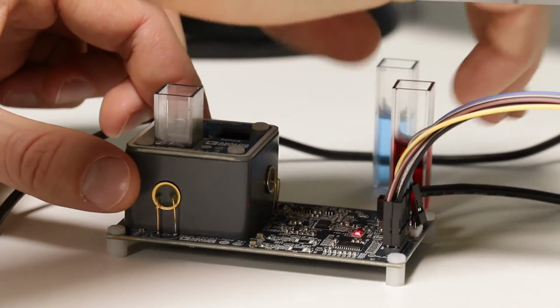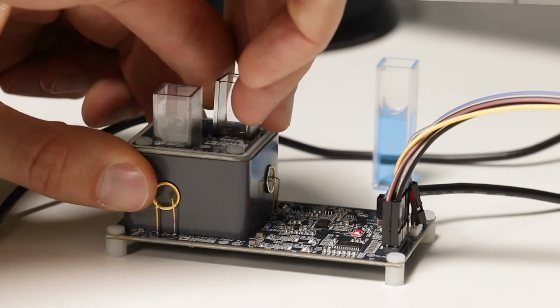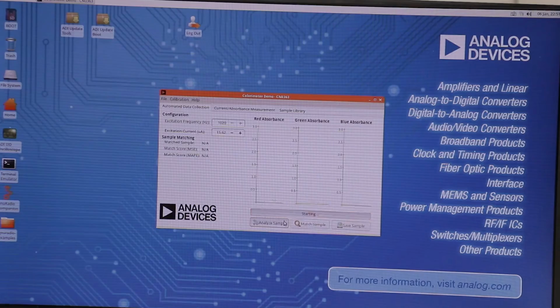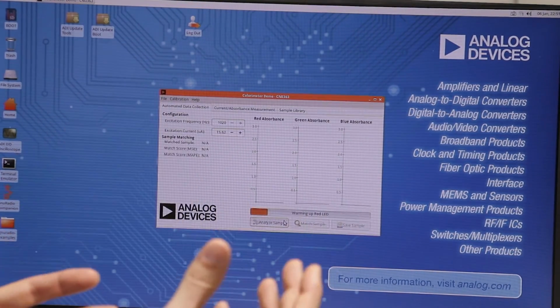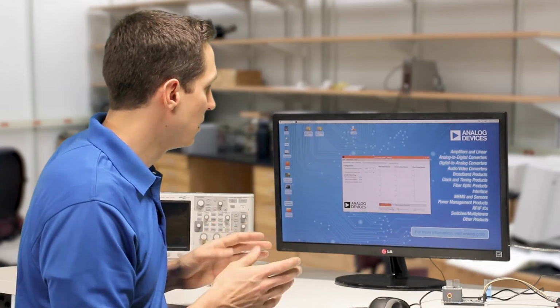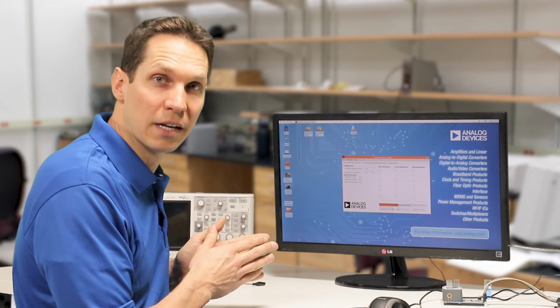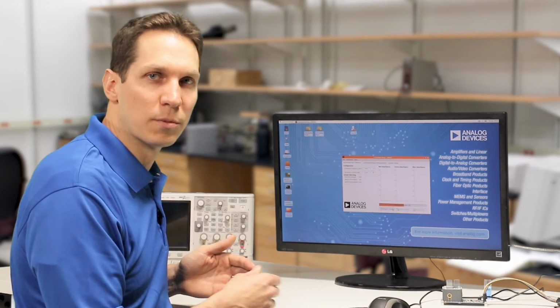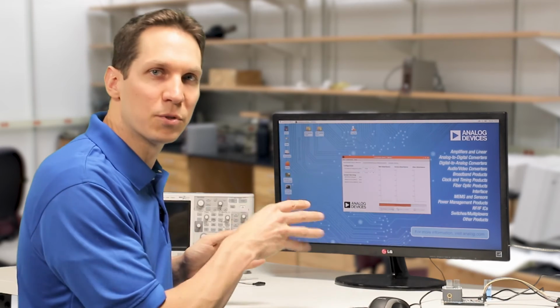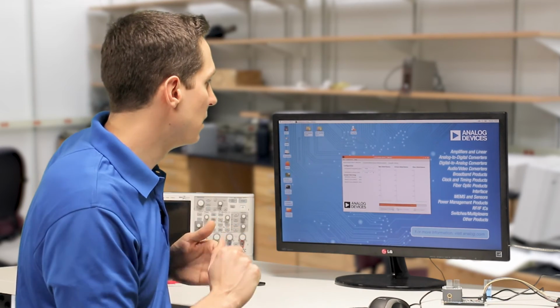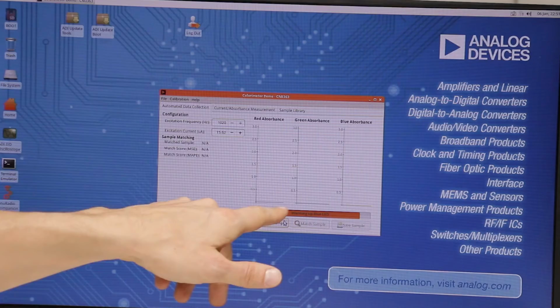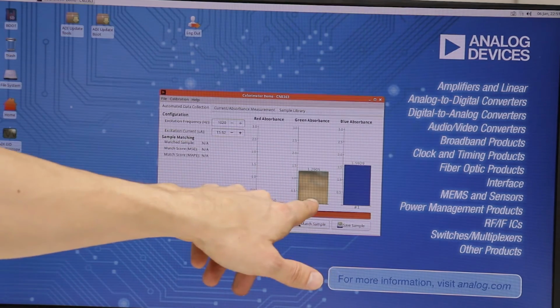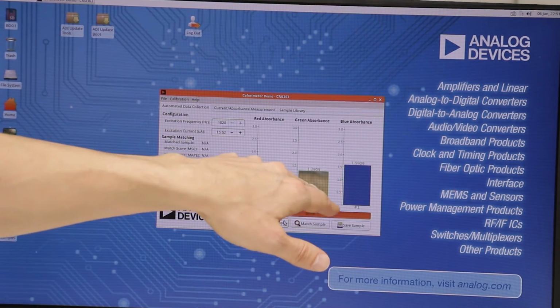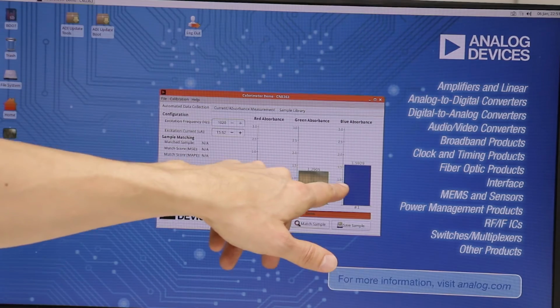So right here in the reference solution, we have distilled water, and then over here we have a red syrup. So as I analyze the sample, it will warm up the three LEDs in line, first doing the red LED, and then it'll also warm up the green and the blue, and it'll take samples after it's done warming up each LED. And after it's taken those samples, it'll display it up here. With the red, I'm expecting green and blue. So green, we've got 1.2905, and blue, we've got 1.529.